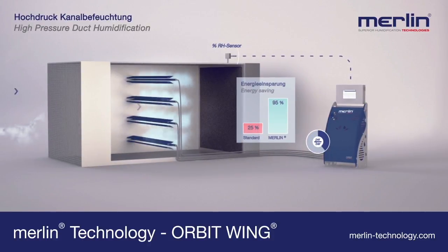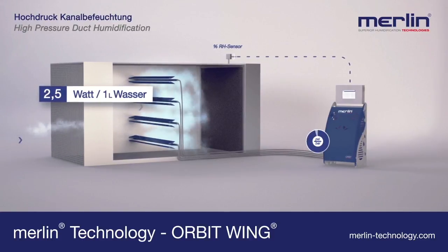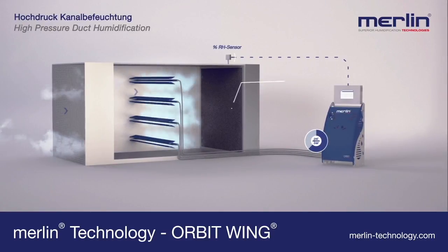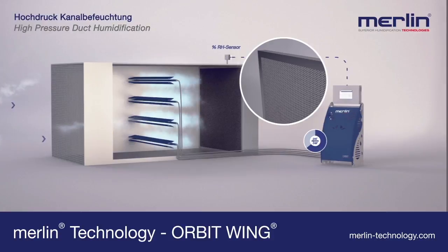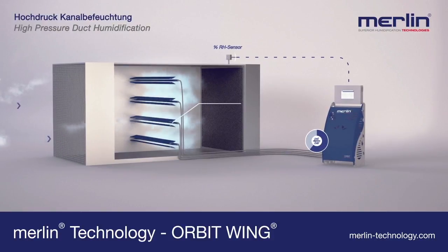Energy savings of 95% are achieved — only 2.5 watts of energy are required for each liter of evaporated water. The high-pressure unit with water hydraulic pump is oil- and maintenance-free. 98% vaporization is guaranteed, and the micro-drop separator made from stainless steel serves only as a safety element.